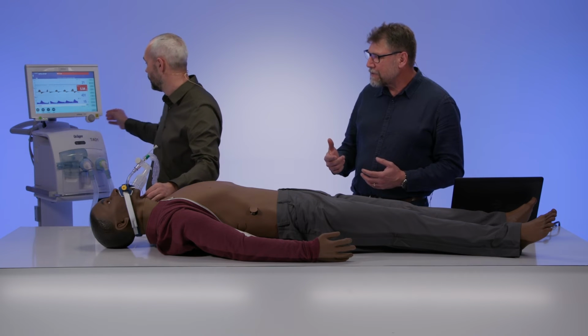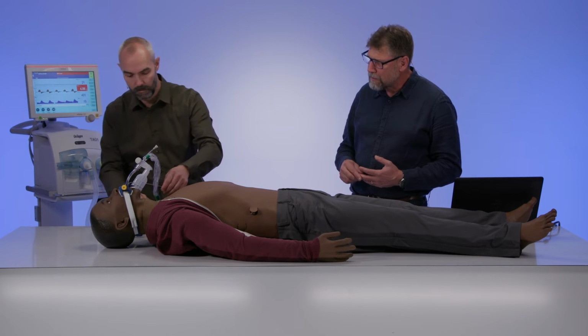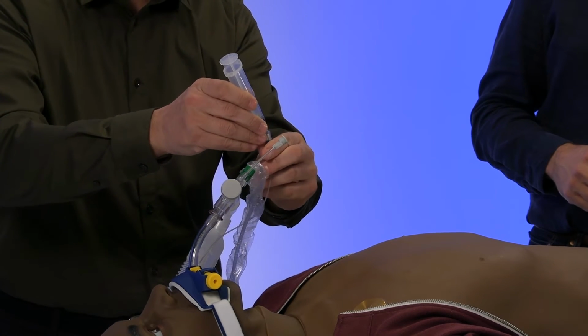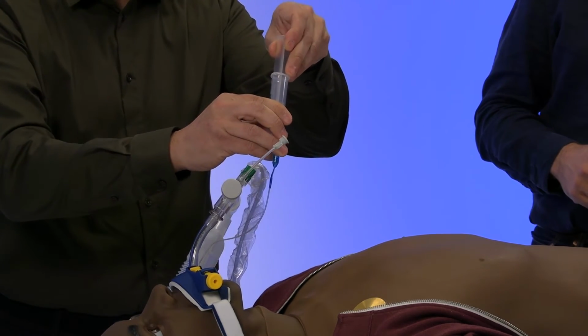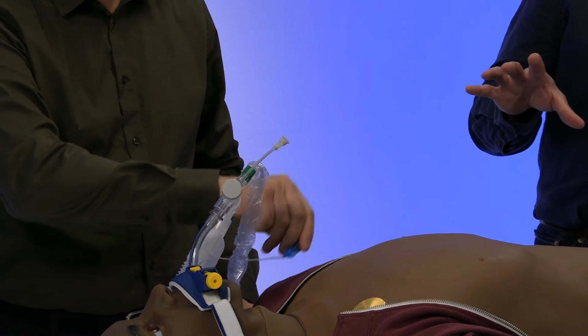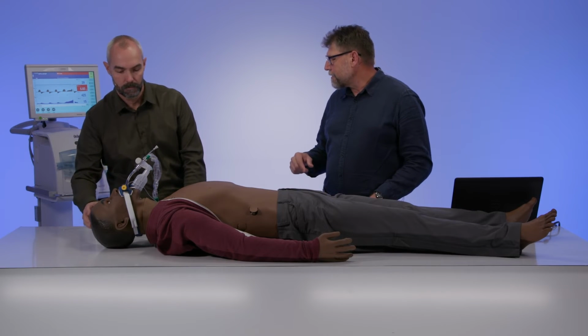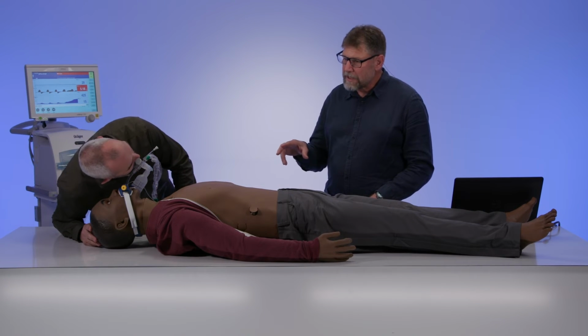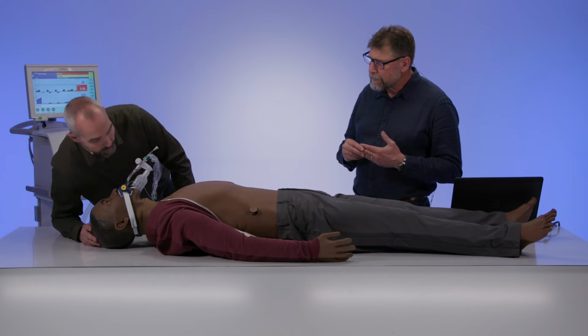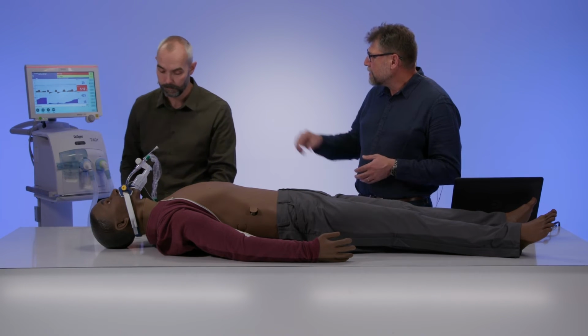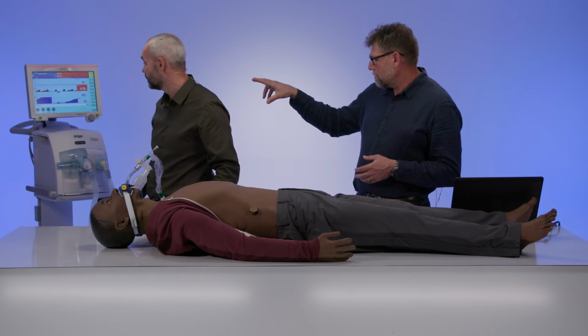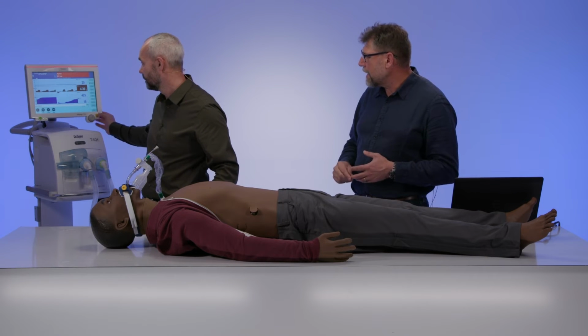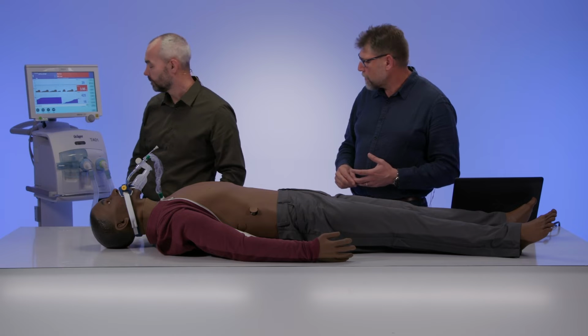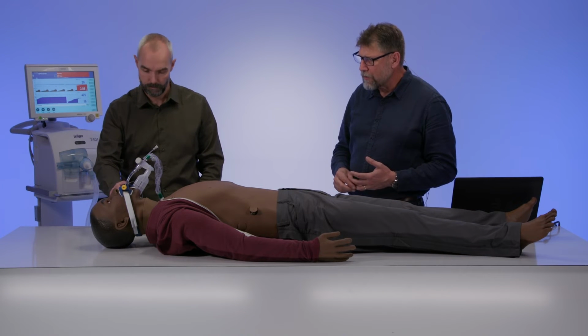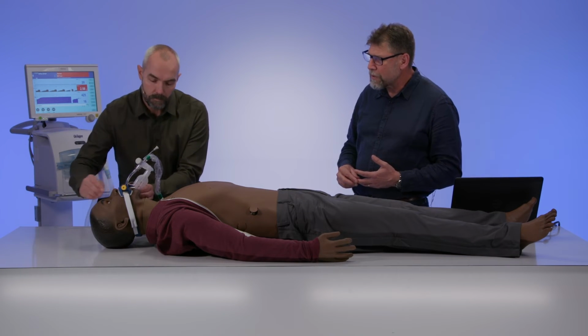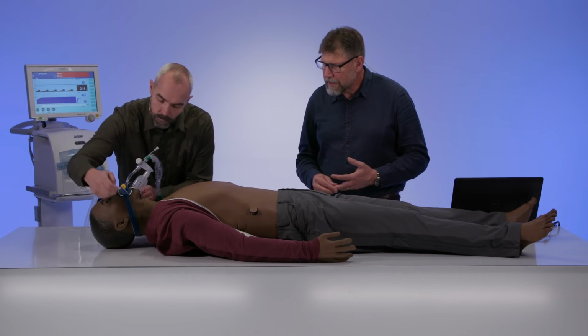So perhaps now we do a cuff check, so if you just release the air in the cuff. Will do. Okay, and now that that's done, one of the things we'll notice on the ventilator is it will start to pick up a leak. You should be able to hear the air escaping. Yeah, I can hear it and I can feel it. Okay, great. So now we can see we're displaying a leak on the ventilator. We've also got a dropping minute volume because we're losing volume. So I think he's ready to be extubated. So perhaps if you remove the Thomas tube holder now.